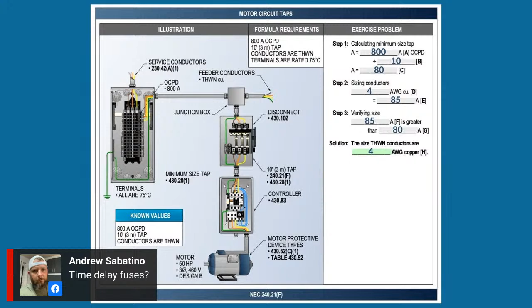And I'll explain to you why. Well, I don't know, that might be pretty close to, that number 4 is going to work perfect. Let me give you an example. Andrew, just to answer Andrew, basically the reason you do time delay fuses is because when that motor's starting, you're getting a high ramp of inrush, and you want that inverse time so that that motor has enough time to start. You're basically arc welding for a few split seconds.